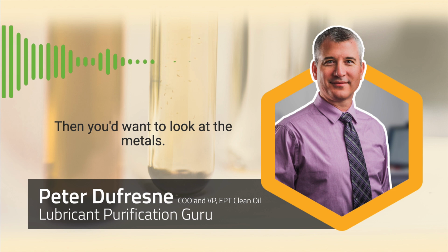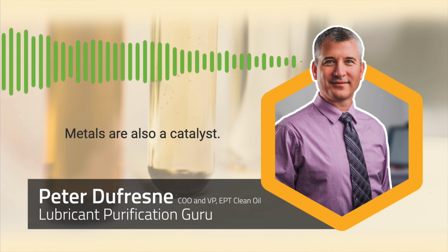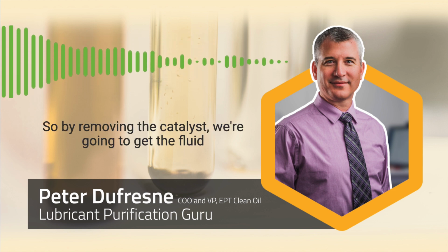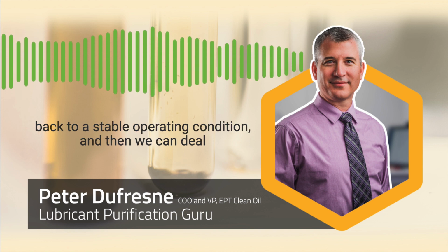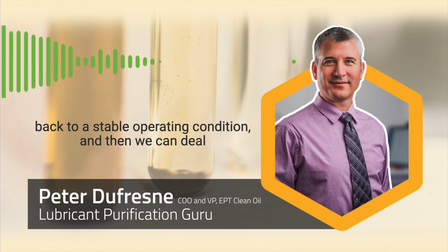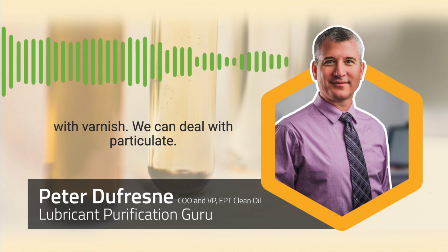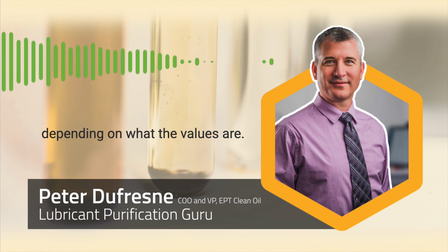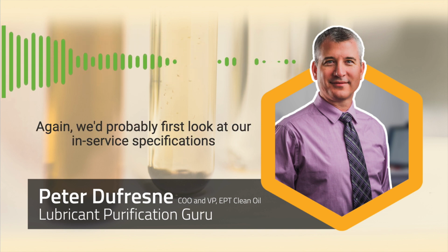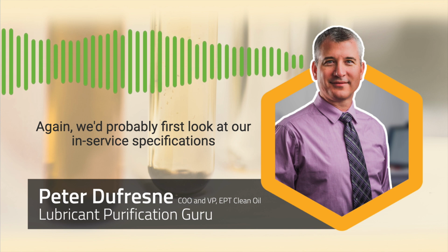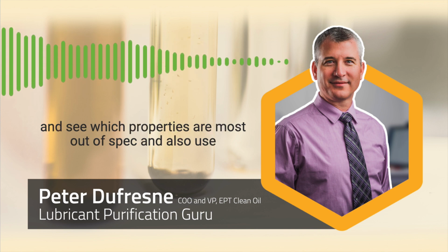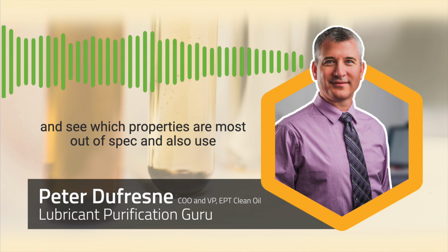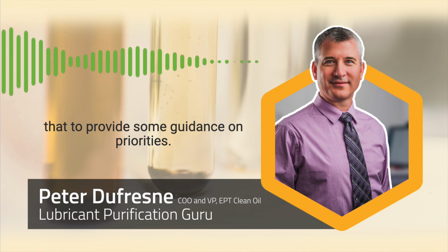Then you'd want to look at metals. Metals are also a catalyst. So by removing the catalyst, we're going to get the fluid back to a stable operating condition. And then we can deal with varnish, we can deal with particulate, we can deal with submicron particulate, depending on what the values are. Again, we'd probably first look at our in-service specifications and see which properties are most out of spec, and also use that to provide some guidance on priorities.